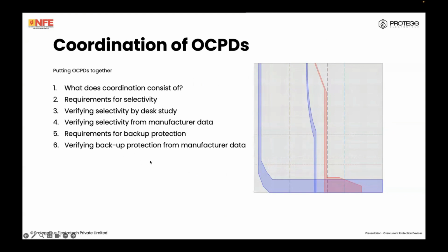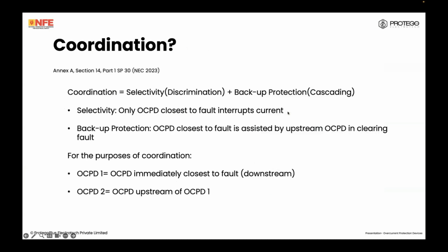Backup protection is a little more complicated, so you can only really verify it from manufacturer data alone, not by desk study. So we look at Annex A, Section 14, Part 1 of our National Electrical Code of India. It will say that there is something called coordination that is a requirement in electrical installations. It is made up of selectivity and backup protection. Simply said, selectivity means only the OCPD closest to the fault interrupts the current. You have continuity of supply in all upstream OCPDs and all upstream circuits. Backup protection is when the OCPD closest to the fault is assisted by an upstream OCPD in clearing that fault.